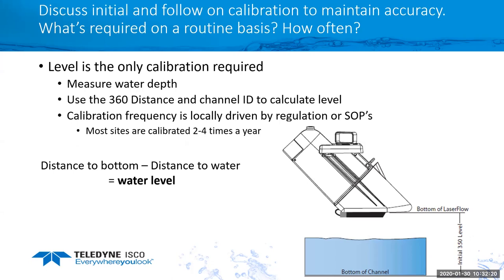If it's difficult to get into the pipe, we can use the distance. So the laser flow sensor will automatically tell you what the distance from the bottom of the laser is to the water surface. But what I recommend is when you install the laser, take a physical measurement of the bottom of the laser to the bottom of the channel. And then when we have the distance reading from the sensor itself, we just subtract it from the overall distance to the bottom of the channel. What's left over is going to be your level.